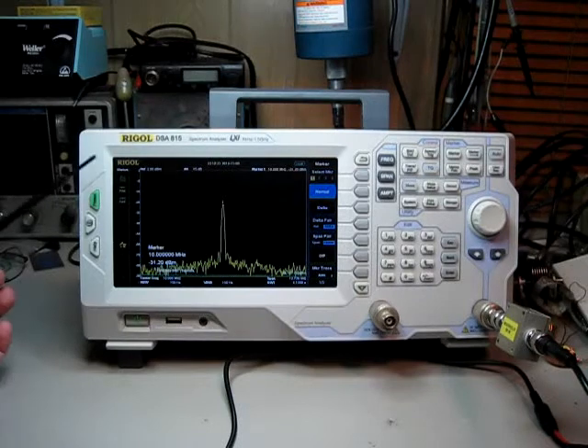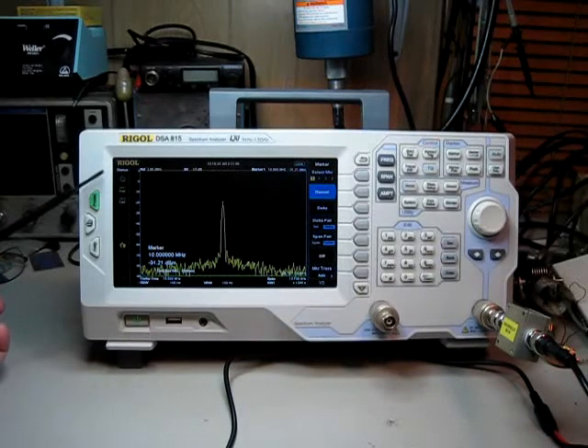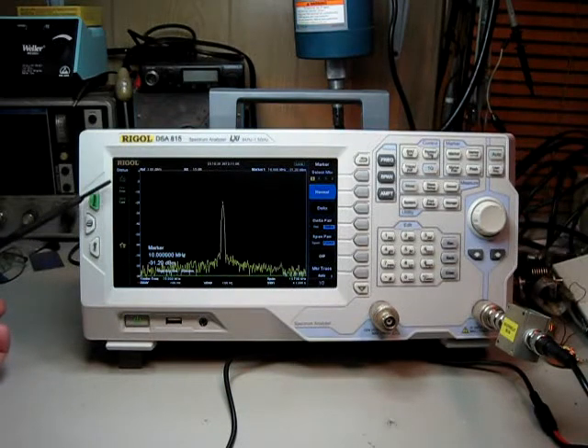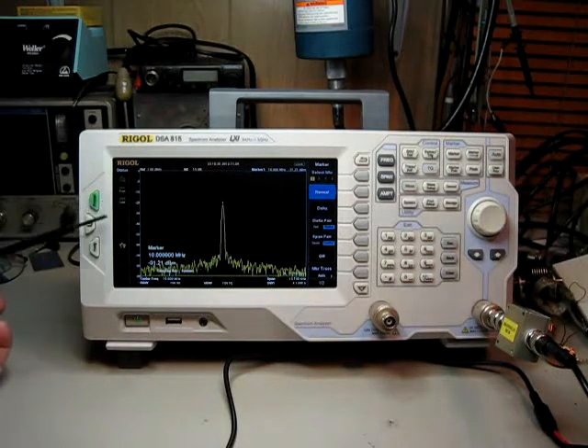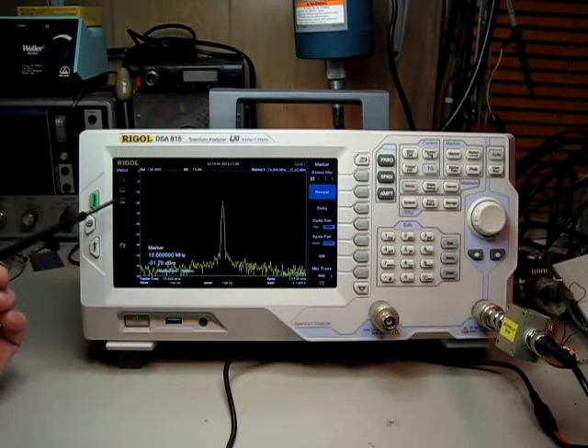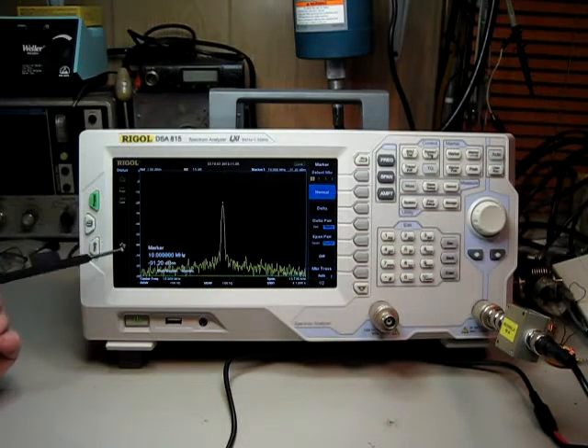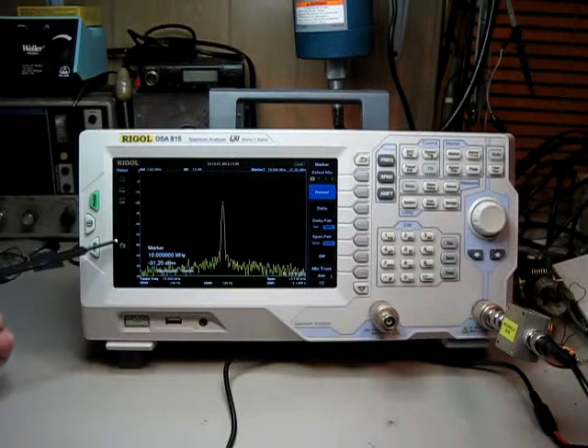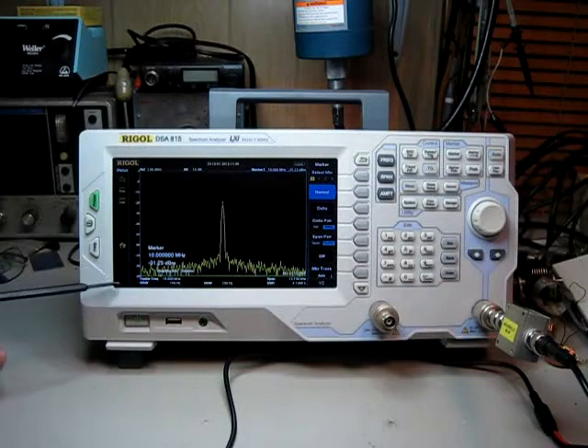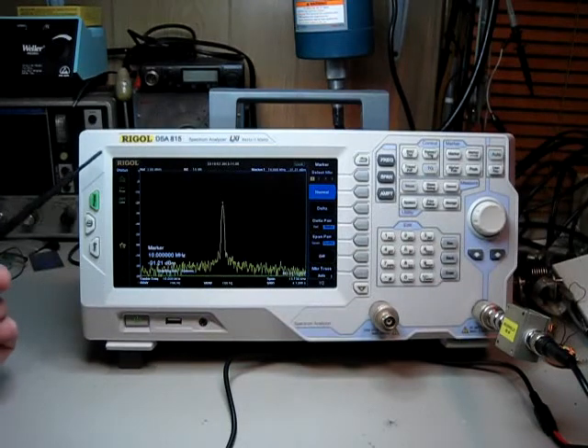On the left side of the screen, there's a status bar, as it were, and it shows different settings and conditions that you have the analyzer set in. Like this one says peak, trigger is free running, sweep is continuous. There's a correction factor one, I believe. Some for the other traces: there's a trace one, trace two, trace three, and a math function that you can perform on the traces, actually, which is a really nice feature.